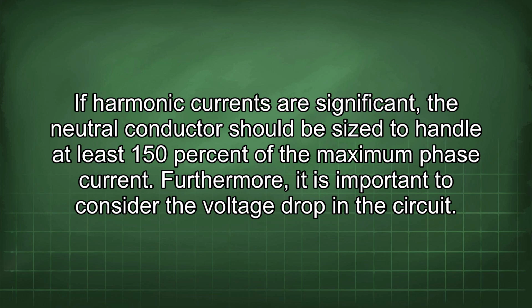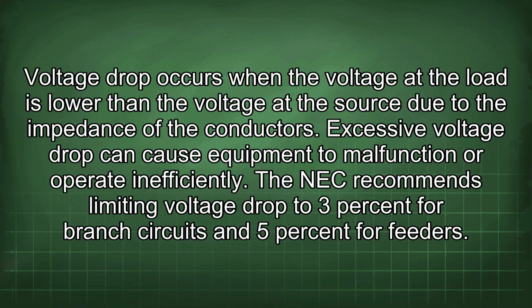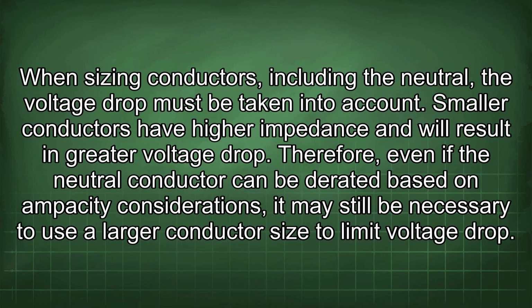Furthermore, it is important to consider the voltage drop in the circuit. Voltage drop occurs when the voltage at the load is lower than the voltage at the source due to the impedance of the conductors. Excessive voltage drop can cause equipment to malfunction or operate inefficiently. The NEC recommends limiting voltage drop to 3% for branch circuits and 5% for feeders. When sizing conductors, including the neutral, the voltage drop must be taken into account.